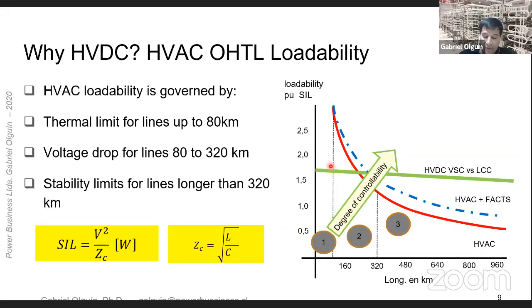The curve shows that the value of power that can be transmitted as a function of the length of the line is decreasing and is limited by three factors: thermal factor, voltage regulation, and stability. Long transmission lines are limited by stability issues and usually not capable of transmitting more than 1 PU, while shorter transmission lines are limited thermally. Therefore, the longer the line, the lesser the loadability. On the other hand, HVDC lines have no limit in terms of transmission capacity.